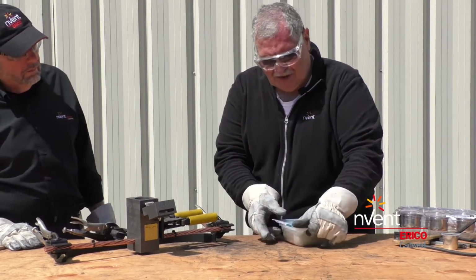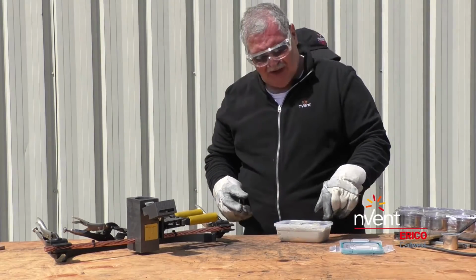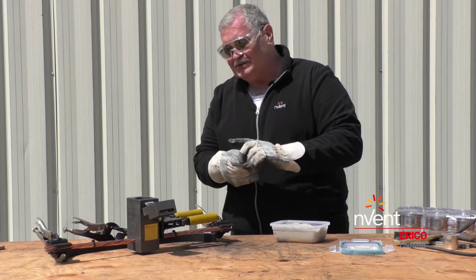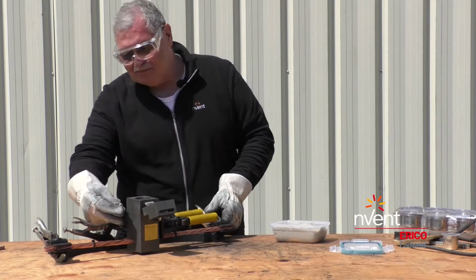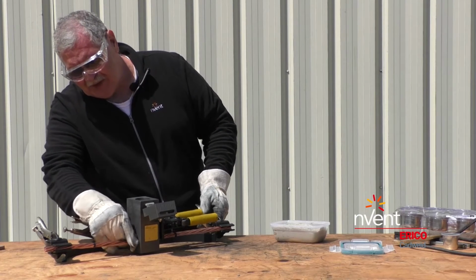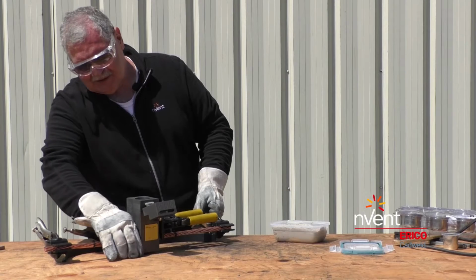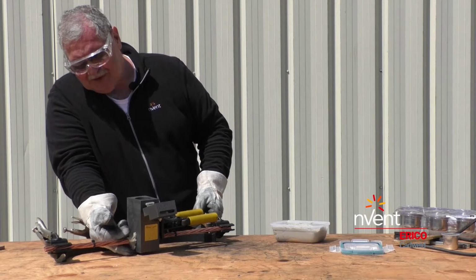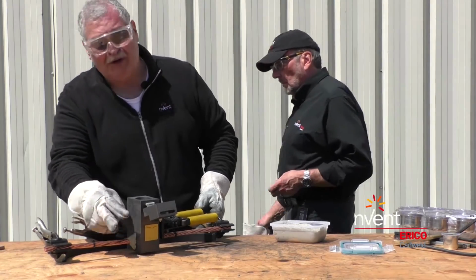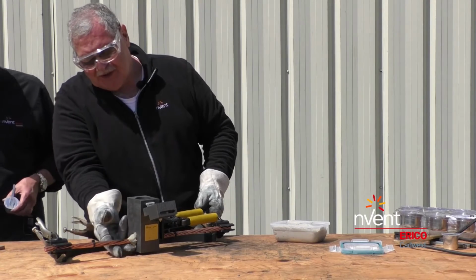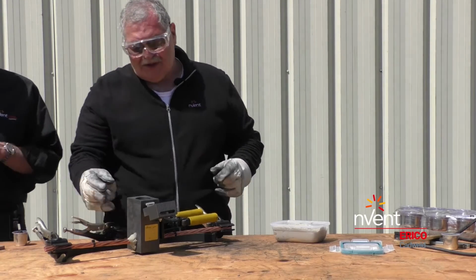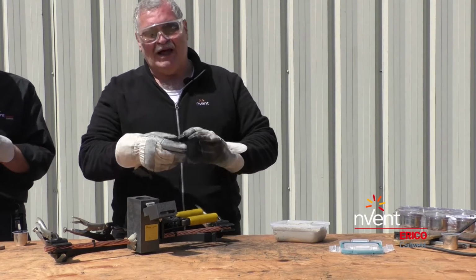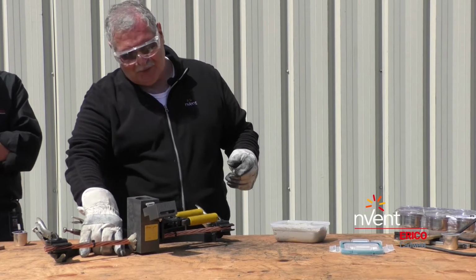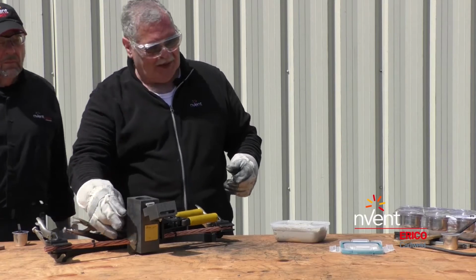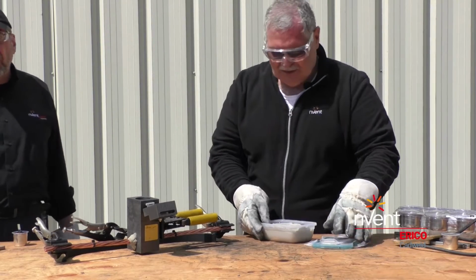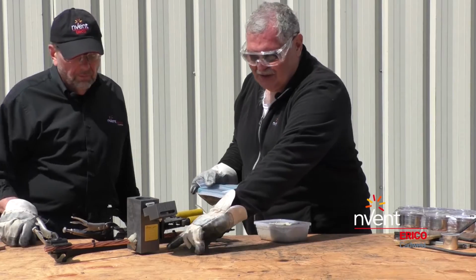One other thing I'd like to talk about is our mold sealer. A lot of times when a mold is used for a long time you may get a little chipping. If you take the mold sealer, T403 I believe, and pack it around the conductor - I'm only going to do one side just to show it - it'll seal up any gaps, especially on a 4/0 strand. If the mold's hot, a lot of times you get weeping and a couple drips coming out, so this will stop that. A lot of times it'll happen with brand new 7-strand cable. You'll probably see it a little bit on this side here.